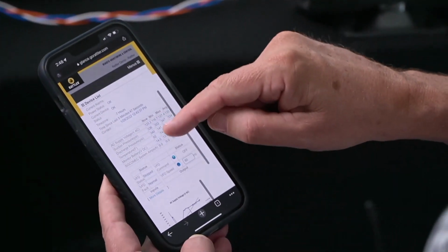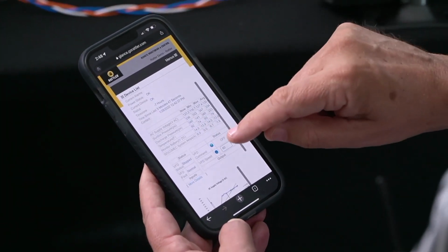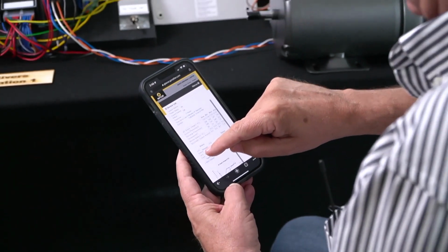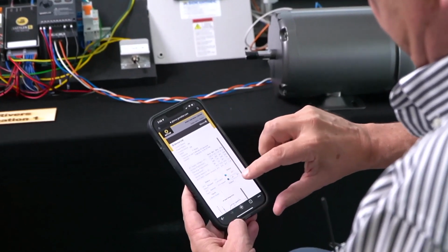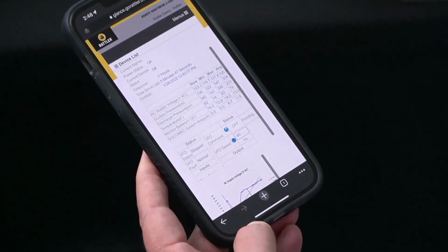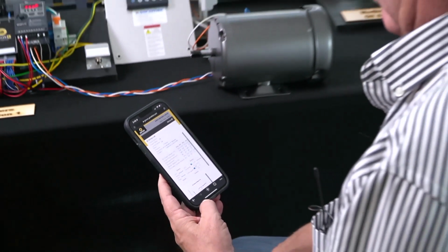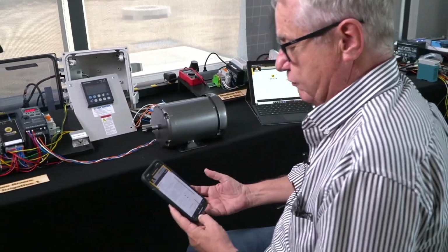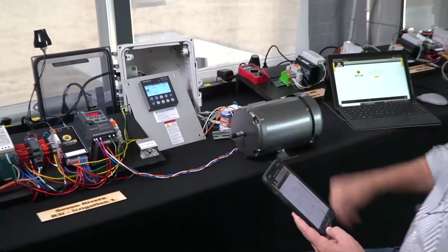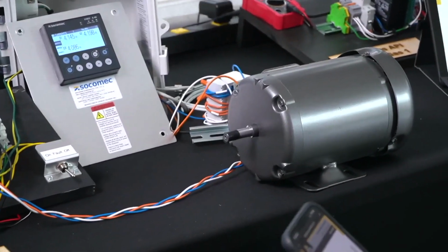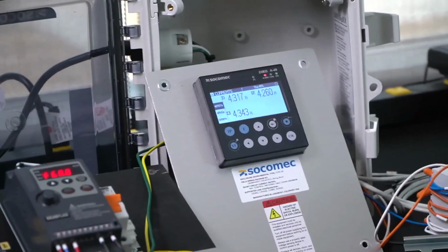You see all the parameters, the current power supply, and the current amperage is 0 because the motor, as you see, is off. The VFD status is showing stopped, and the VFD command is currently off. You can click this blue button over here, and that changes to pending, which shows that it's sending down the command to change the state of the VFD from off to on. And that turns the motor on, as you can see, and this is the current that's being drawn by the motor, shown on the Socomec meter.